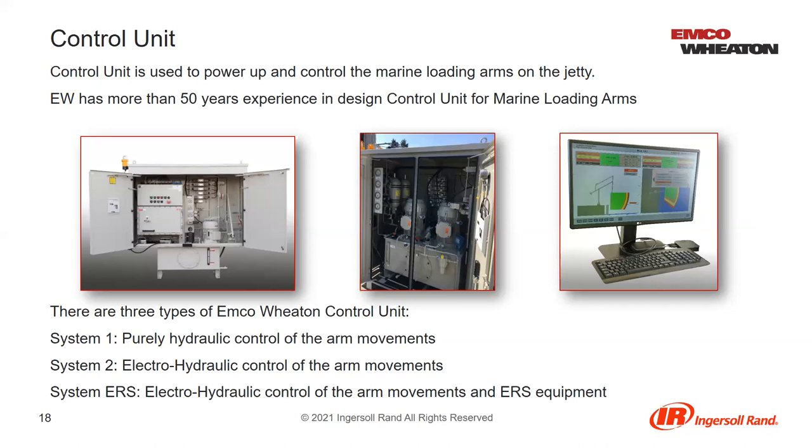And then the last one is the system ERS, which controls the movement of the arm and also is responsible for the emergency disconnection. So part of that system are also accumulators to have enough hydraulic energy to do the emergency release whenever there is power loss on the jetty.